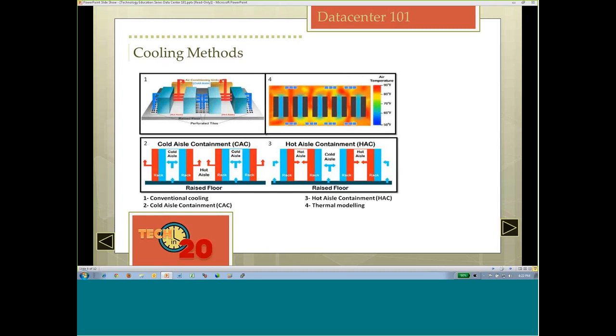And obviously, for air temperature, you want to monitor it. You can see this one shows cold aisle containment in the center with the blue, and being able to monitor that within the data center, you understand where your heat is and is not. Those maps change throughout the day, because as you ramp up different things within the data center, like batch jobs or other usages, you'll see these maps actually morph throughout the day.